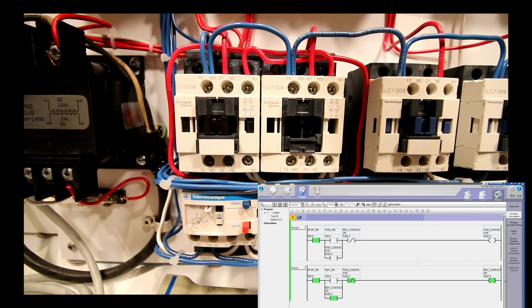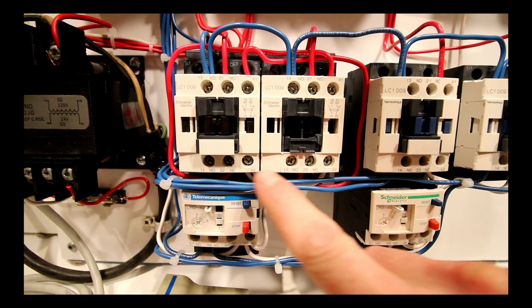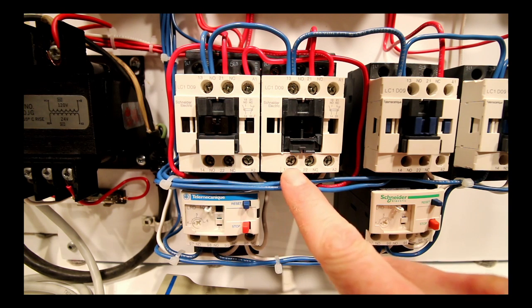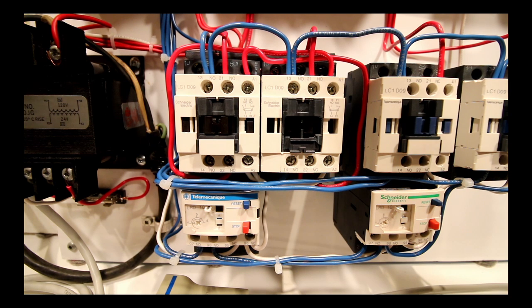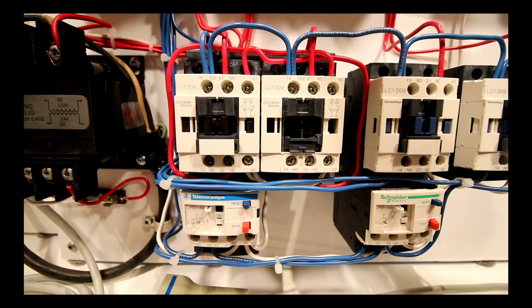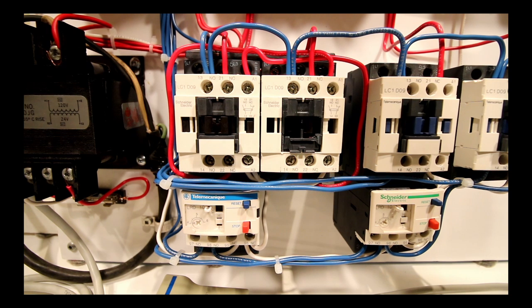We need to fix this program — there's nothing to indicate when an overload actually occurs, and nothing is shown on the program. Right now we're relying on the internal bit to keep the holding contact and keep that contactor pulled in. On the next video we're going to do a closed loop, making use of the holding contacts on the forward and reverse, the two normally open contacts, and also the normally open contact on the overload to send a signal into the PLC. That covers the forward-reverse open loop — any questions or comments, leave them below.